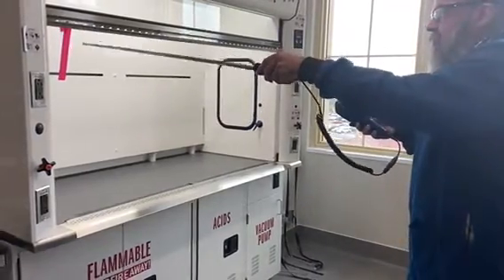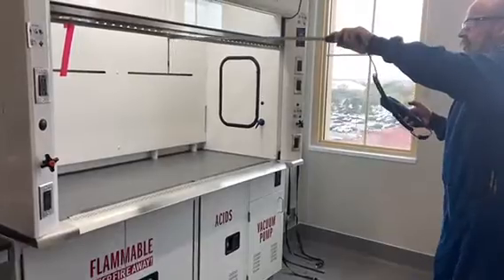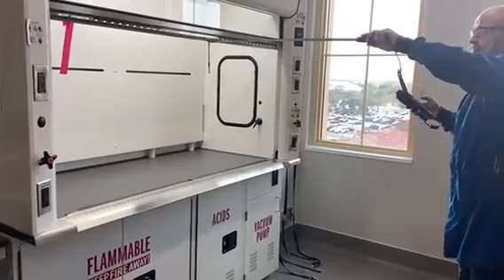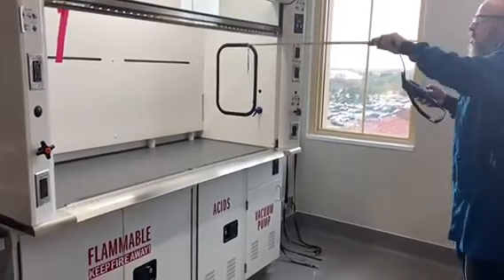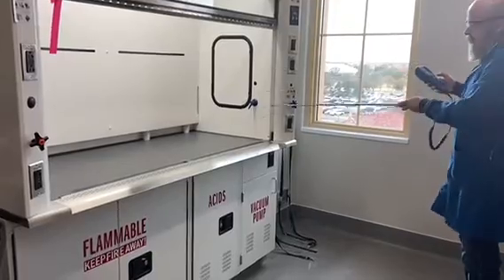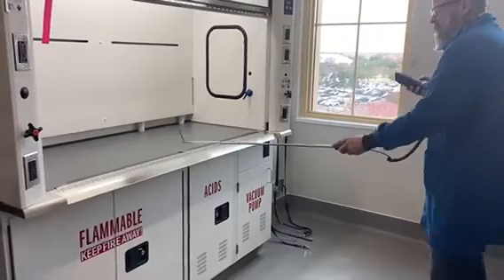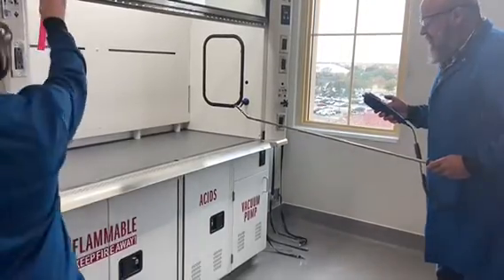We're going to do it now. Make sure we don't get too close to the edges, and try to maintain the depth. It's also important to keep the meter very still while doing this process. That's nine samples — I'm going to go ahead and do eleven because it's a larger plate. This one averaged out at 77 feet per minute.